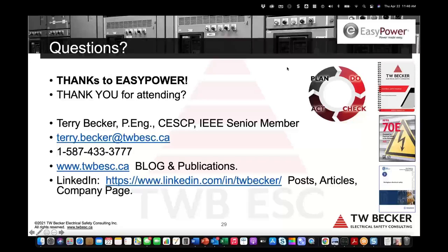Okay, so here's another question. What's the difference between DC and AC PPE? There is no difference. So for DC arc flash, the results are the same, a calculated incident energy, right? So the DC formulas that are in EasyPower, the results are the same. There's a defined working distance, you'll calculate incident energy, and it's the incident energy value that's on the label that the worker uses to determine the arc thermal performance value of arc flash PPE, right? So the formulas are different, DC versus AC, but the results are the same.